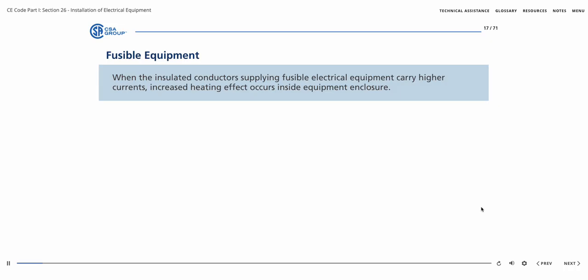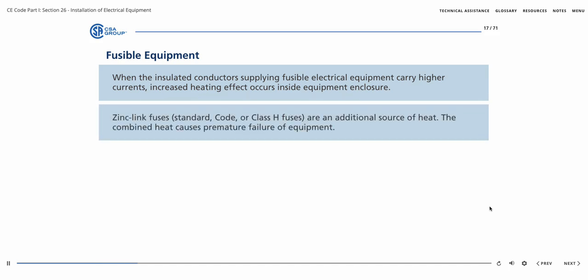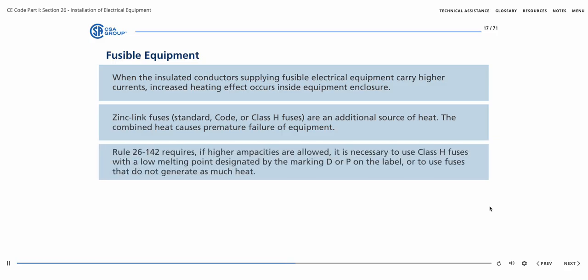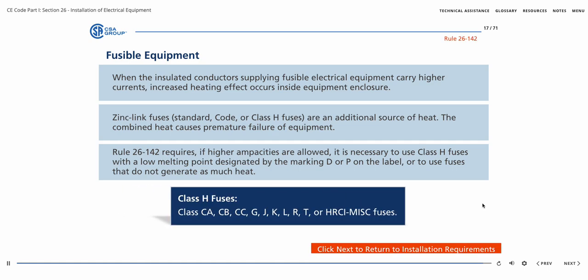When the insulated conductors supplying fusible electrical equipment are allowed to carry higher currents, an increased heating effect occurs inside that equipment enclosure. Zinc link fuses, usually referred to as standard or code fuses, now known as Class H fuses, are an additional source of heat, and the combined heat can cause a premature failure of the equipment. Therefore, Rule 26-142 requires, if higher ampacities are allowed, it is necessary to use Class H fuses with a low melting point designated by the marking D or P on the label, or to use fuses that do not generate as much heat, such as listed in the box on the screen.